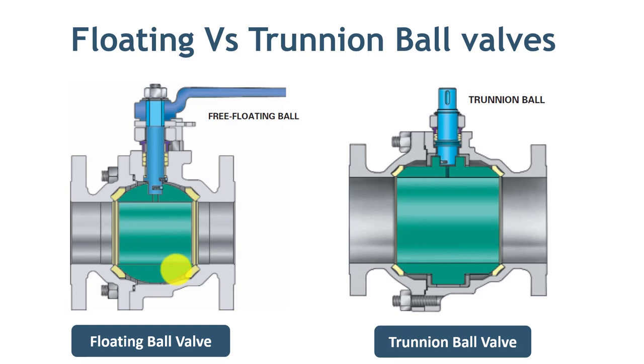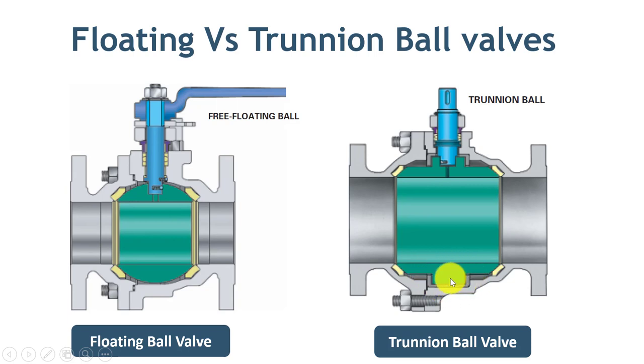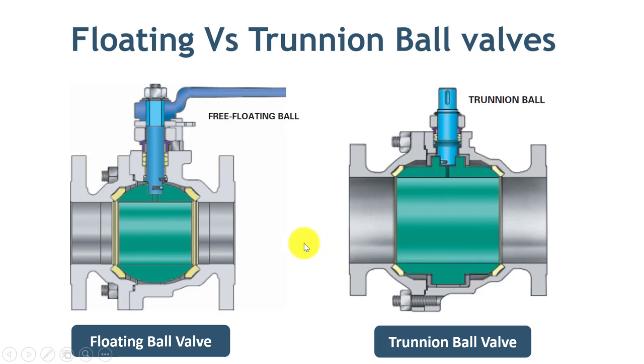On the other hand, in a trunnion-mounted valve, the ball will remain in position irrespective of the fluid pressure. The valve seats are designed so they always stay in contact with the ball to provide the required sealing. You can open this valve more easily compared to a floating type, but you have to trade off some of the benefits of high sealing.